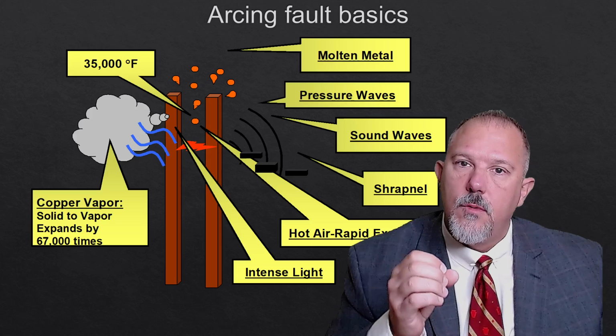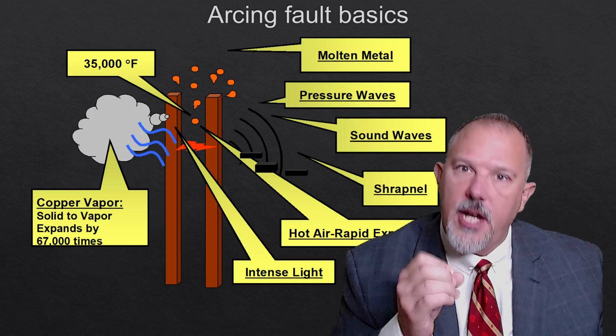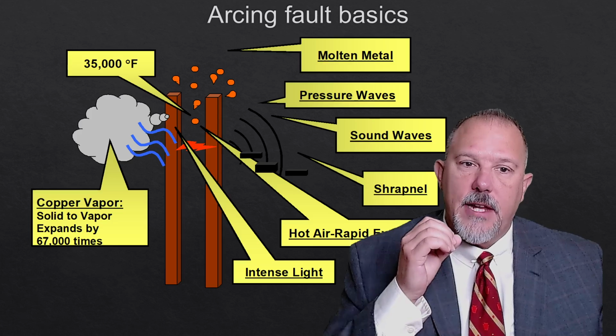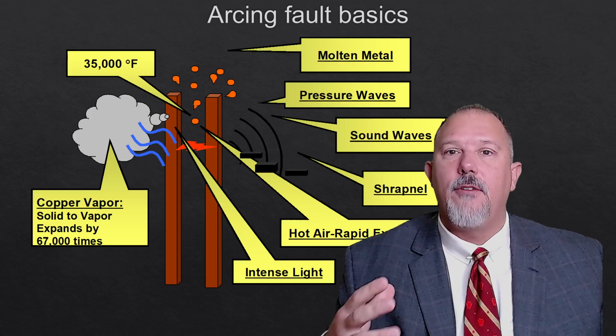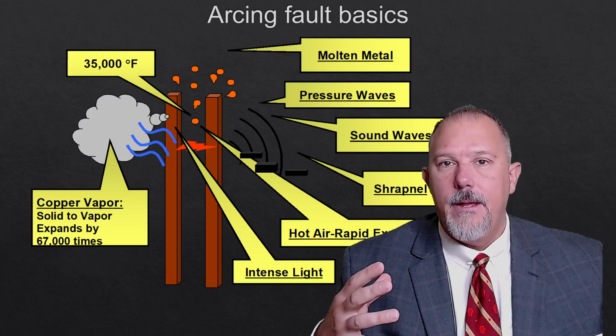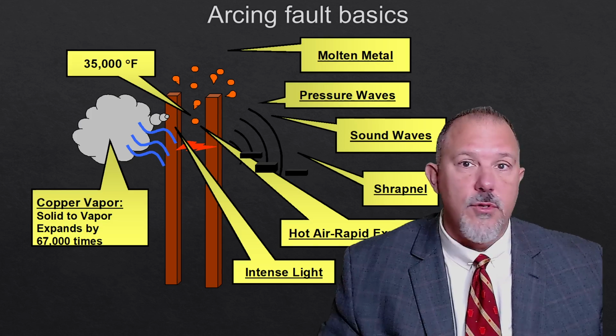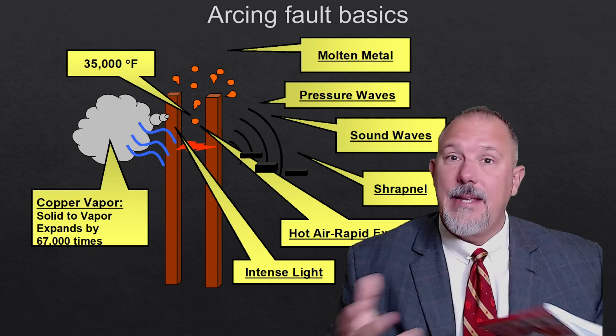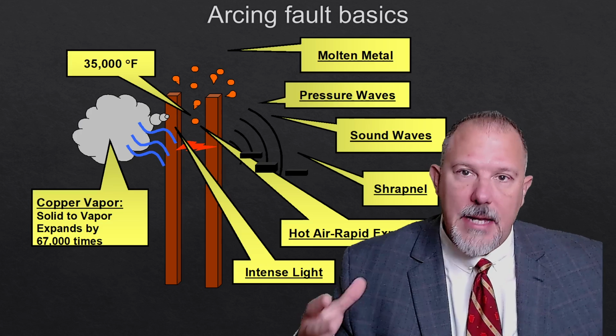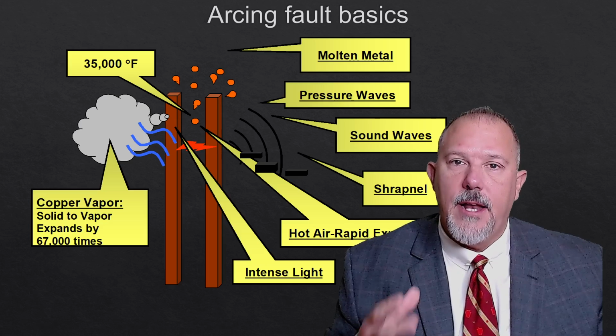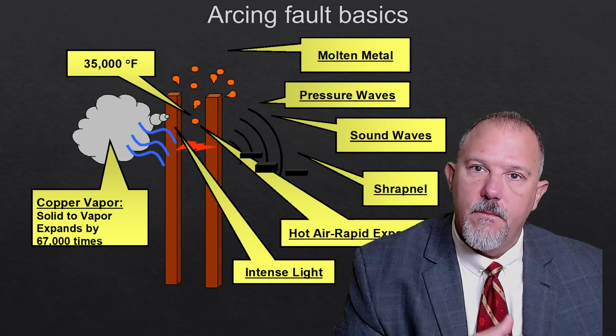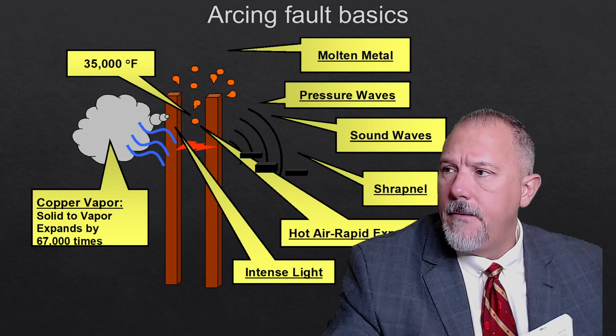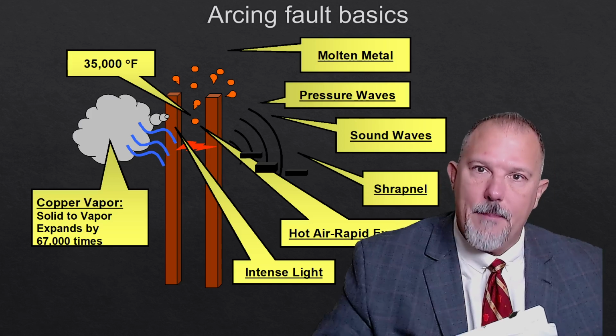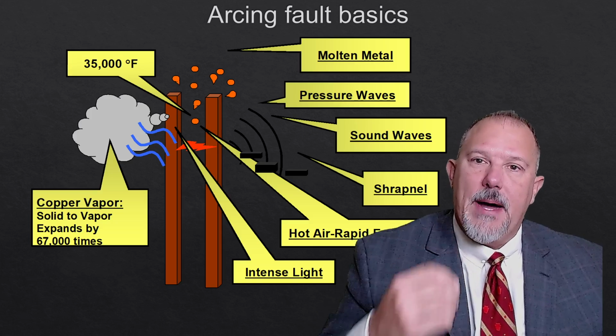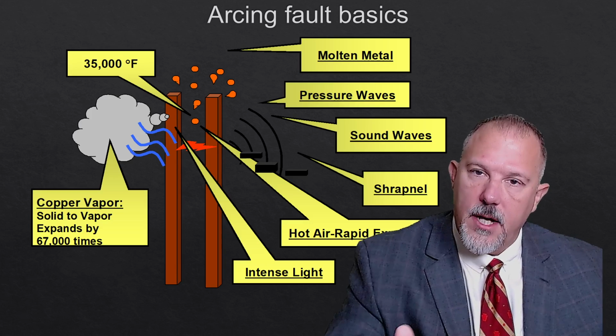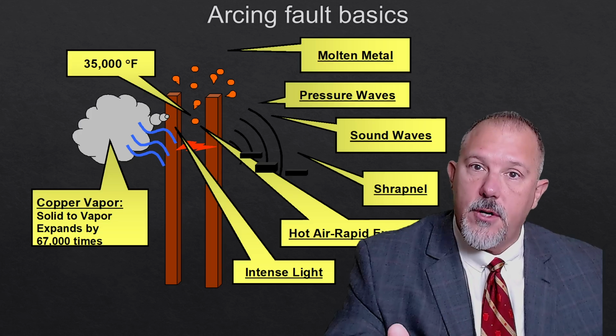So when you see two conductors like this that are side by side, the initial event will create a chain reaction, and that chain reaction develops a cloud of ionized air, which includes vaporized metals, portions of metals, plastics, steel, copper, all that great stuff is just in the air, which creates an avenue for current to flow, phase to phase to phase. Now, that's an important thing to remember. You've got to understand what happens. And we'll talk a little bit about that force and where that force comes from. It comes from voltage. It comes from the available fault current that is there.